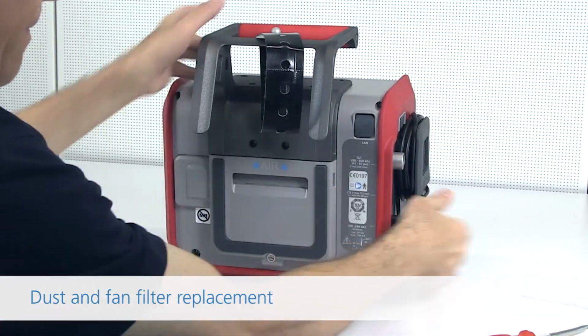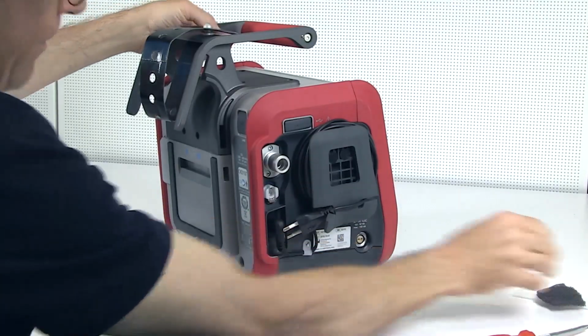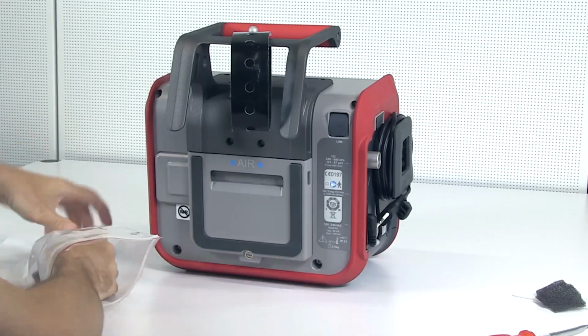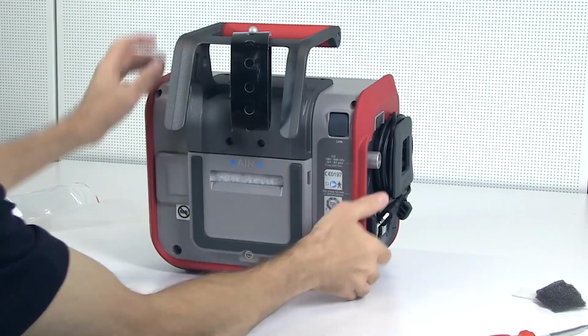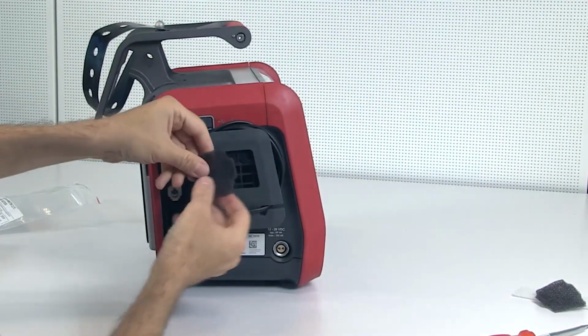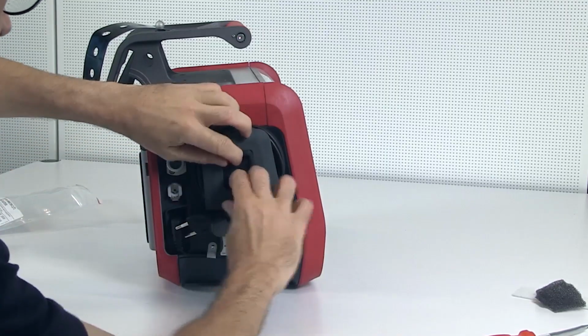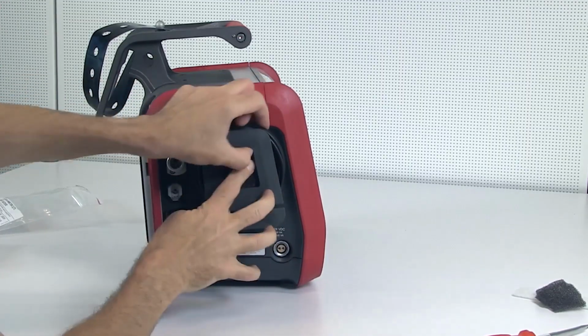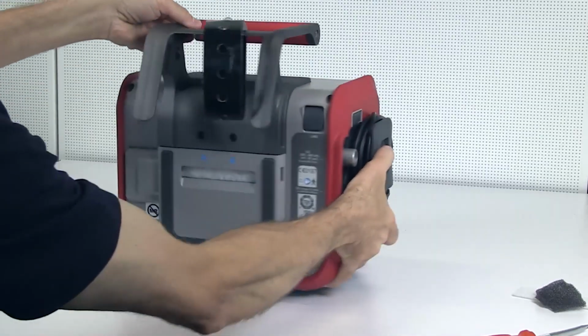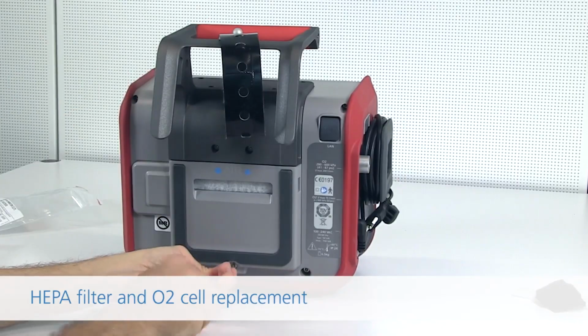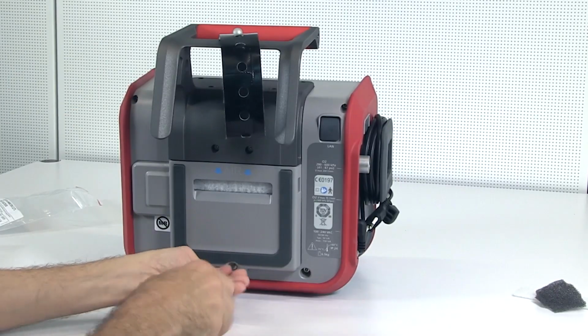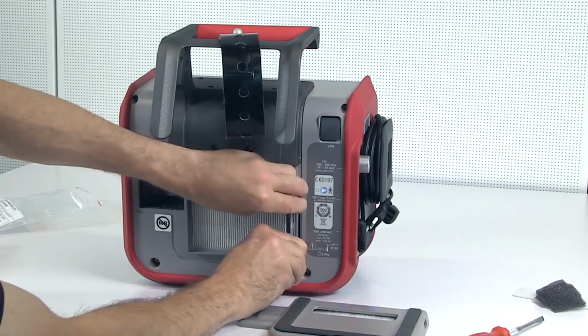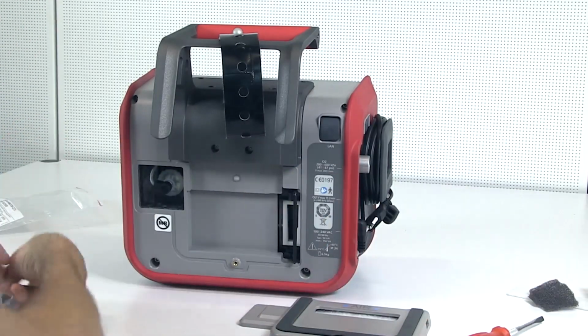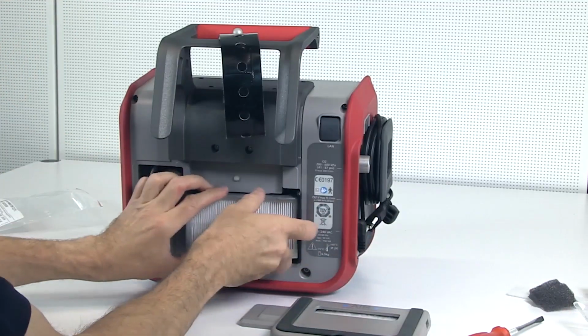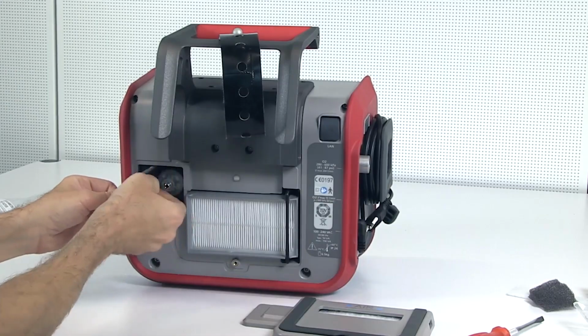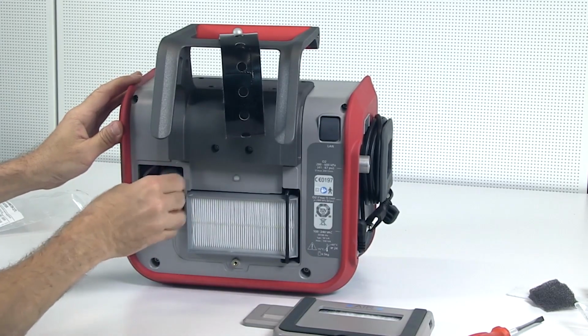Replace the dust filter and the fan filter. Open the filter cover. Replace the HEPA filter. Unplug the connector from the oxygen cell, then unscrew the oxygen cell and replace it with a new one.